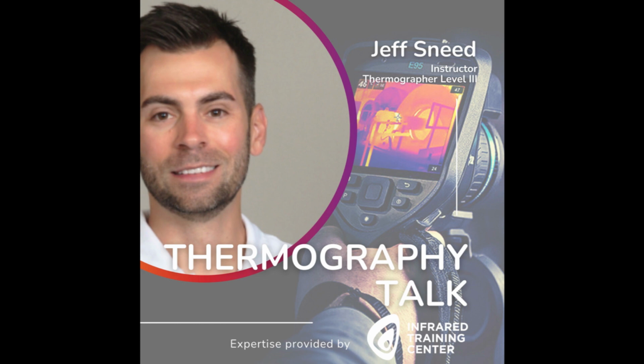All right. Typical working distance, generally speaking, is around 18 inches, and that's really a statement for under 600 volts. So lower voltage equipment, it's around the 18 inches section. This could be a benefit of using thermography, because we can be way further back, much further than 18 inches, and be able to perform the inspection, but this is specifically talking about if you're going to be contacting it.